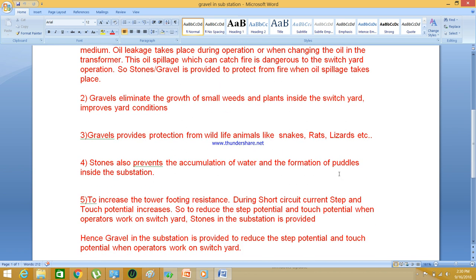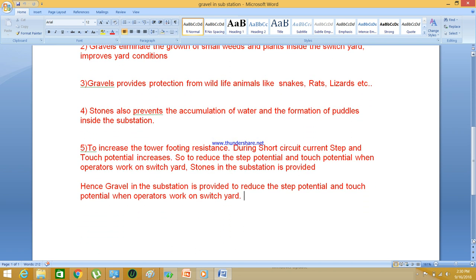A fifth important reason is that gravel increases the tower footing resistance during short circuit current, thereby minimizing the step and touch potential. I have made a separate video on step potential and touch potential — you can have a look at it. When you place gravel in the substation, the step potential and touch potential will be reduced, thereby safeguarding personnel.